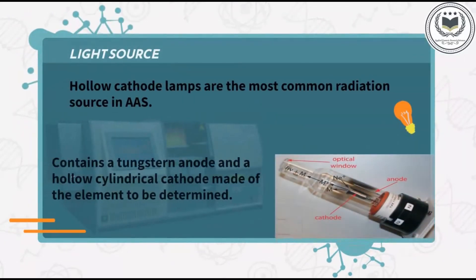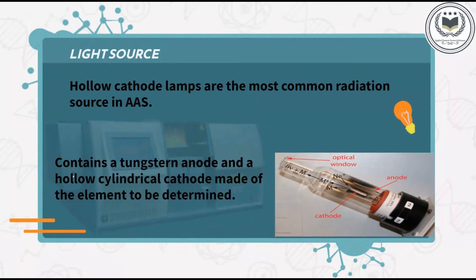Hollow cathode lamps are the most common radiation source in AAS. We need a continuous source of radiation in the AAS instrument. The extreme narrowness of the absorption line in the sources causes problems, so we use a hollow cathode glow discharge lamp to give sharp emission lines for a specific element in atomic absorption spectroscopy instrumentation.